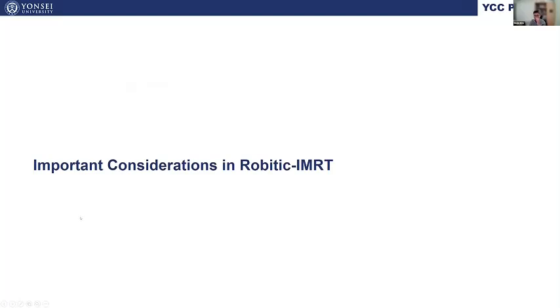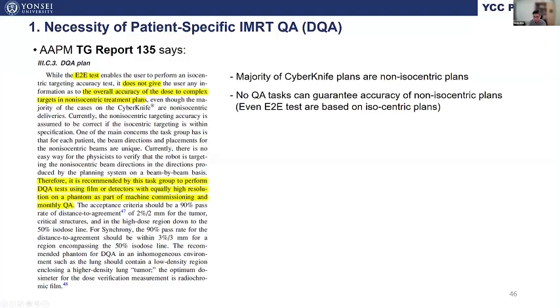Finally, I'm going to wrap up my presentation by talking about some important considerations of robotic IMRT. The first issue is patient-specific QA. The AAPM TG report 135 emphasized the need for patient-specific QA. In fact, most CyberKnife plans are non-isocentric, but there's no periodic QA task to ensure the accuracy of non-isocentric plans. Even E2E tests are not sufficient for this issue. Thus, the TG report says that patient-specific QA is the only way to guarantee the accuracy of non-isocentric plans.